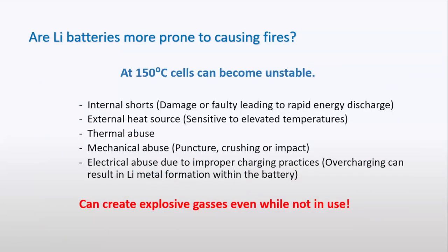Are lithium batteries more prone to causing fires? I'm not going to say yes outright, because I'll get slaughtered by some attendees in this meeting. But I will say that at 150 degrees, the cells can become unstable. Internal short circuits happen in these batteries, and external heat sources will harm them. Thermal abuse, mechanical abuse, electrical abuse - these batteries can create explosive gases even while not in use. I won't call it self-ignition, since that's not actually a real term in fire chemistry.